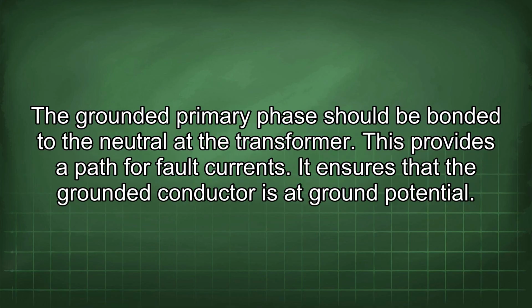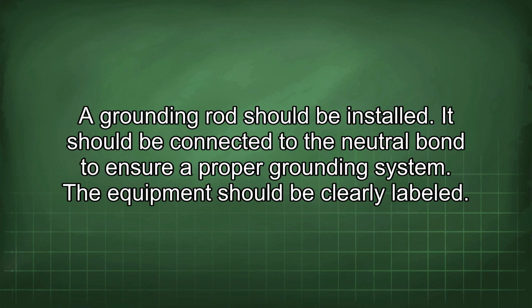The grounded primary phase should be bonded to the neutral at the transformer. This provides a path for fault currents. It ensures that the grounded conductor is at ground potential. The grounding rod should be installed. It should be connected to the neutral bond to ensure a proper grounding system.